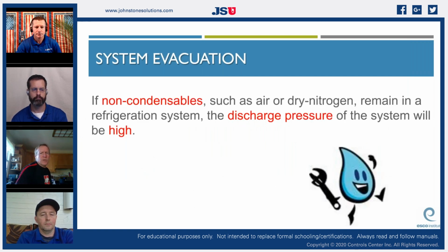If non-condensables such as air or dry nitrogen remain in the refrigerant system, discharge pressure of the system will be high. Believe it or not, any non-condensable will cause your head pressure to be high.